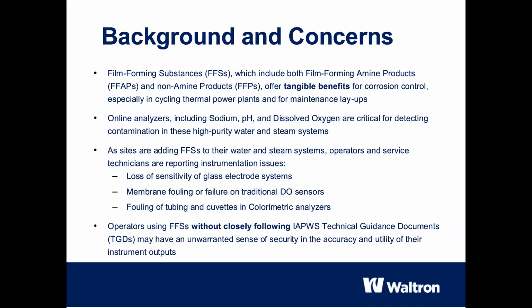At the same time, we rely on high-precision online analyzers to monitor our water-steam cycles. Sodium, pH, and oxygen meters are our first line of defense against contaminants that can cause serious damage. Here lies the problem. Since operators began using FFAPs, reports of problems with the instruments have increased. We hear about loss of sensitivity in glass electrodes, membrane fouling in oxygen sensors, and contamination in colorimetric analyzers.